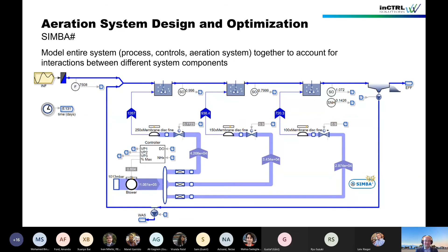And basically when you add control to one of these, a plant, you suddenly have created interaction between the air supply and the air demand. If you didn't have control and you were just supplying air, the only interaction would be you watching what happens and then potentially deciding to make a change manually. But there really isn't any real interaction. Once you put the controls in place, you've essentially created interaction and you've created feedback. And that's when you really need to pay attention to the dynamics.